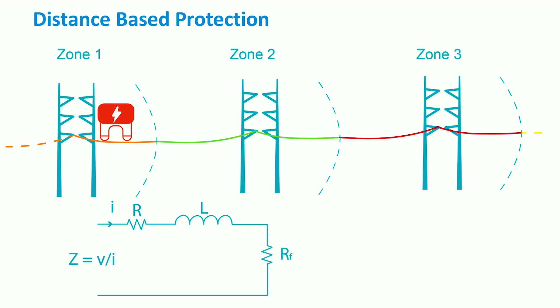During the fault case, when the measured or calculated impedance is lower than the set impedance, the distance relay trips the circuit breaker. Distance protection can be affected by distributed generation and loads, as the measured impedance is a function of the in-feed currents.